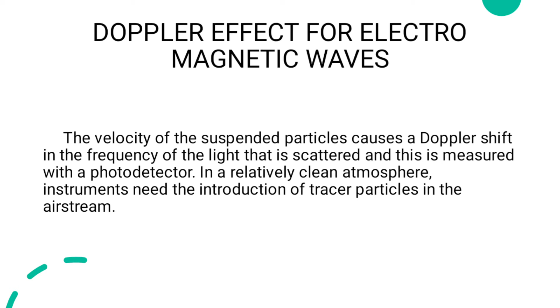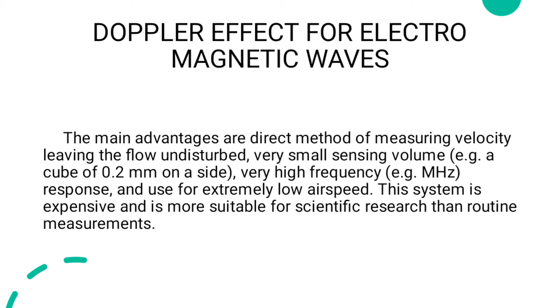In a relatively clean atmosphere, instruments need the introduction of tracer particles in the air stream. The main advantages are a direct method of measuring velocity, leaving the flow undisturbed, a very small sensing volume, for example a cube of 0.2, and very high frequency response, for example in the MHz range, and it can be used for extremely low airspeed. This system is expensive and is more suitable for scientific research than routine measurement.